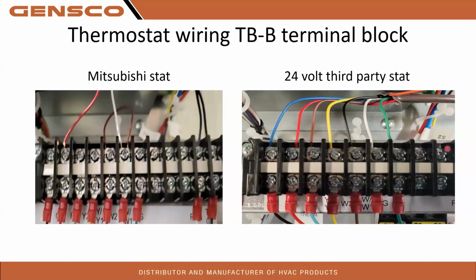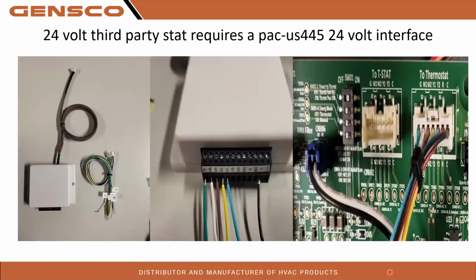If you're using 24-volt thermostats, your Honeywell stats, Ecobees, Nest, that kind of stuff, it is going to wire to that TBB terminal block. And it's going to just be like normal, color for color. You see right here, I have this set up for a 2-stage. There's my Y2 and my W2. So that's where your 24-volt stat is going to connect. It's not going to connect to a PAC 445 in this application, but the 445 is still required, which is actually right here. So if you guys are doing a 24-volt stat, yes, the PAC-US445 is required to do so. So this is the 445.